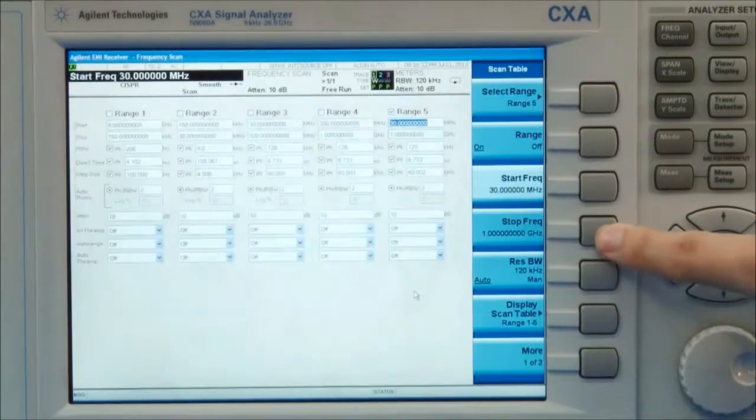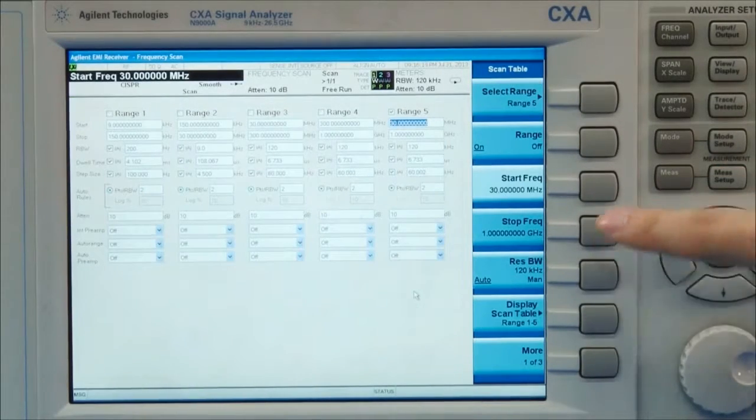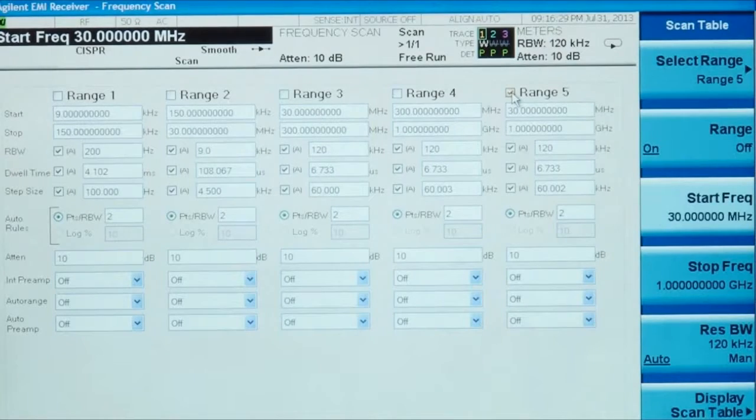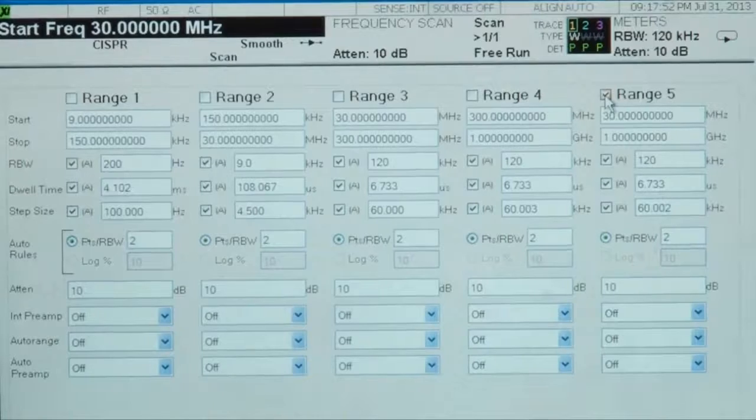It has pre-defined test ranges according to EMI standards. Here, we chose range 5, 30 MHz to 1 GHz.